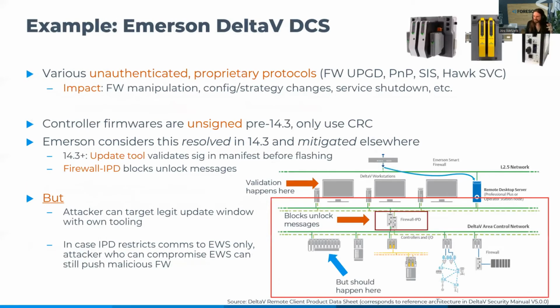An example where this doesn't go completely right are the Emerson DeltaV DCS controllers. These controllers speak a variety of unauthenticated proprietary protocols between the controllers themselves, and between workstations and servers and the controllers. These protocols allow starting and stopping the controller, firmware manipulation, configuration changes, and so on. In addition, prior to version 14.3, controller firmwares are unsigned and only use CRC.